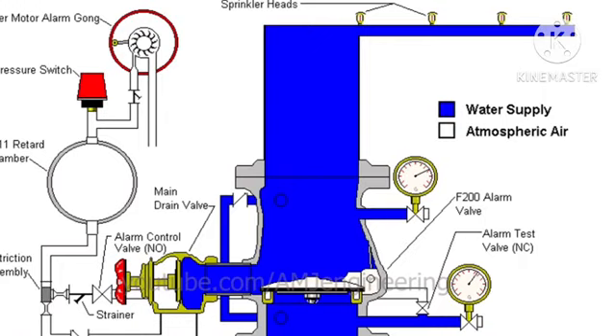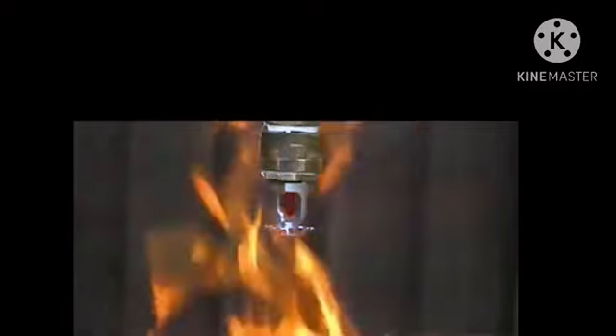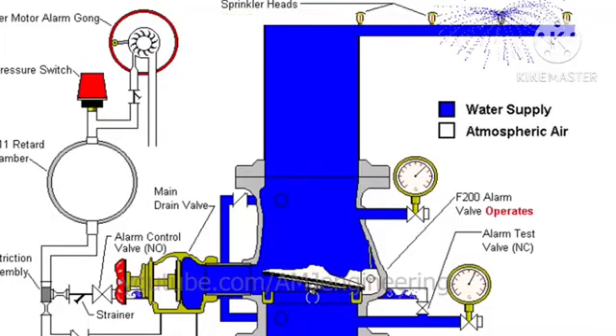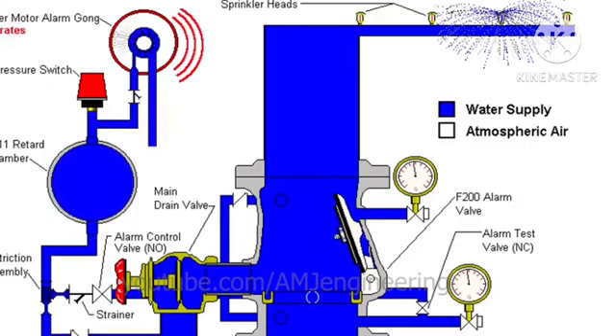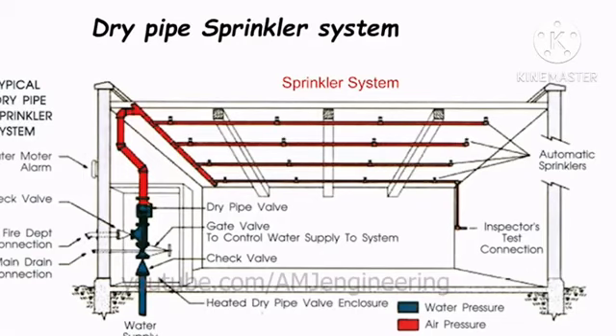Wet pipe sprinkler systems always contain water in the riser and piping. As soon as a sprinkler head activates due to the heat of a fire, water is immediately discharged through the open head. Dry pipe fire sprinkler systems. Dry pipe systems are very similar to wet pipe systems with one major difference. The pipe is not constantly filled with water. Instead, the water is held behind a dry pipe valve, usually some distance away from where the sprinklers are located.